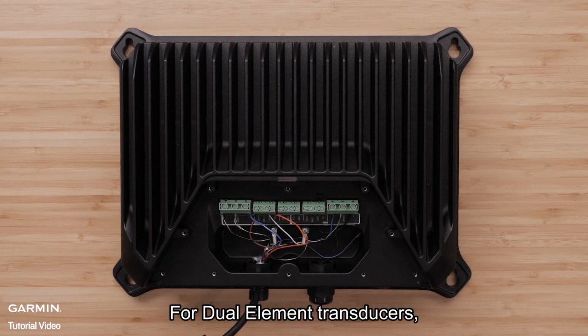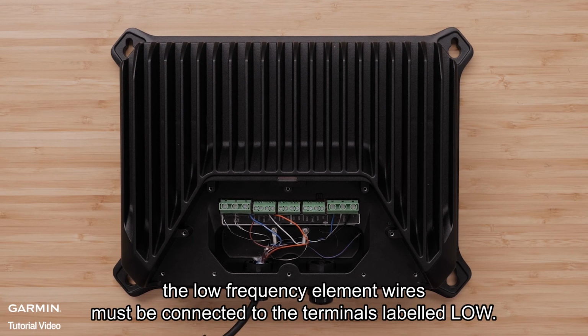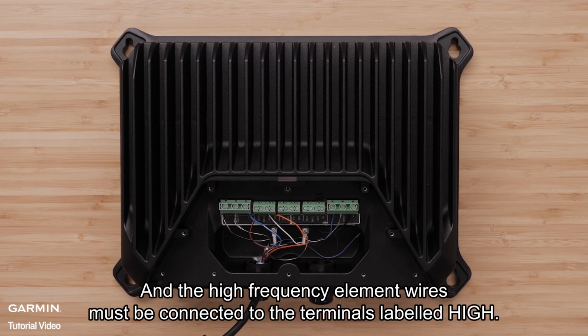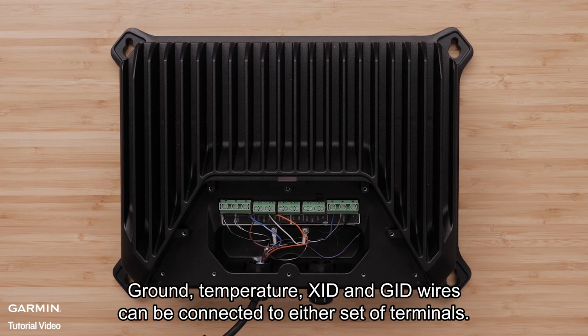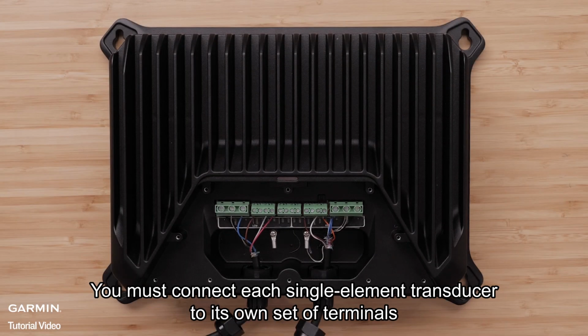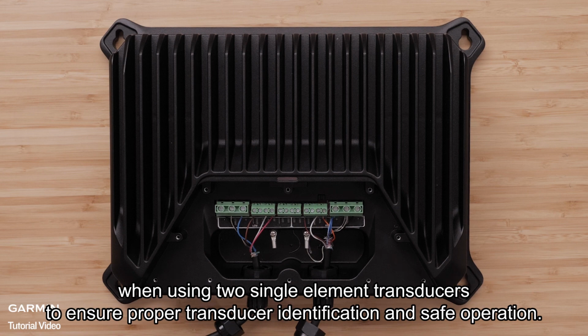For dual element transducers, the low frequency element wires must be connected to the terminals labeled low, and the high frequency element wires must be connected to the terminals labeled high. Ground temperature, XID, and GID wires can be connected to either set of terminals. You must connect each single element transducer to its own set of terminals when using 2 single element transducers to ensure proper transducer identification and safe operation.